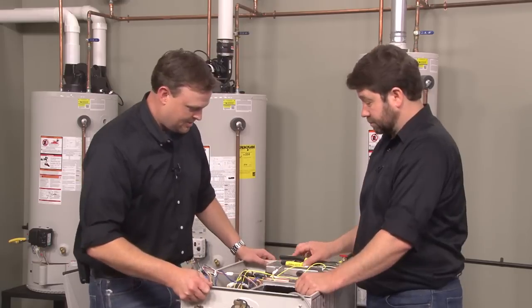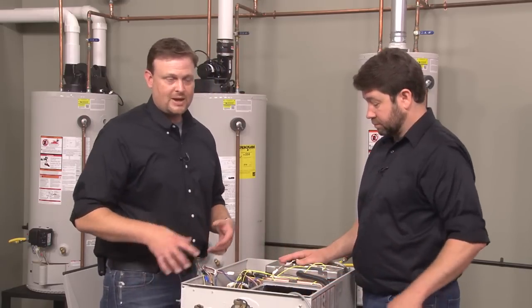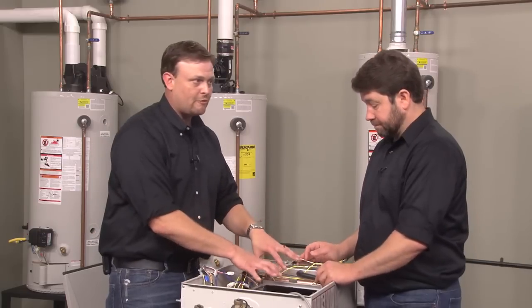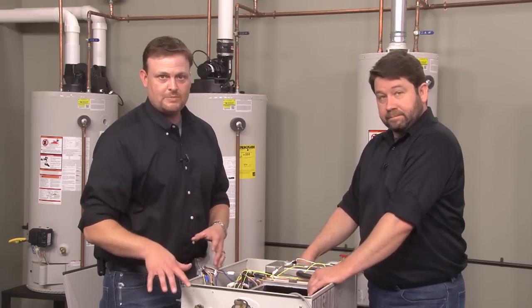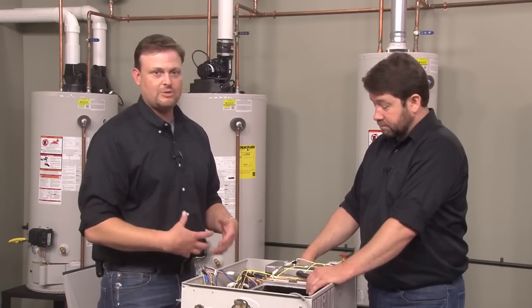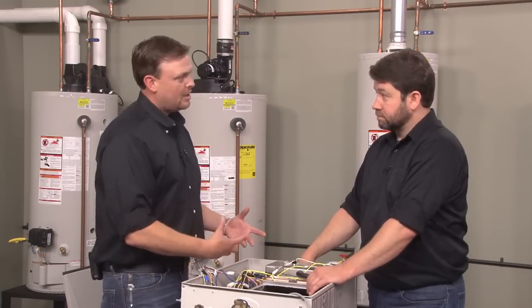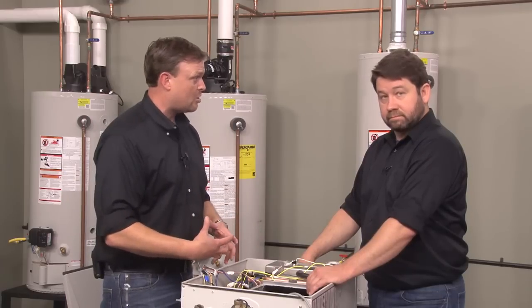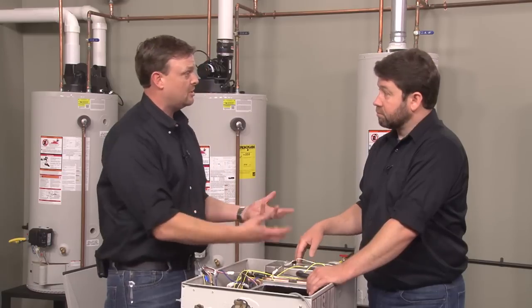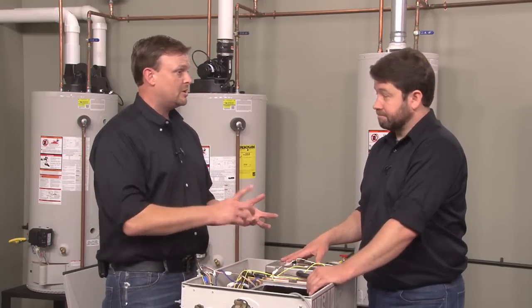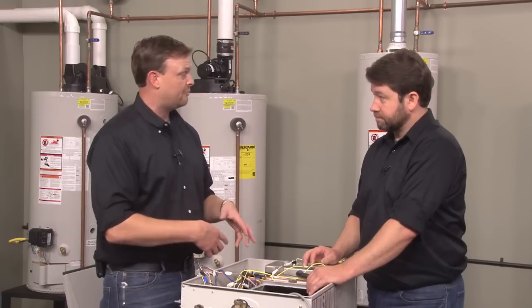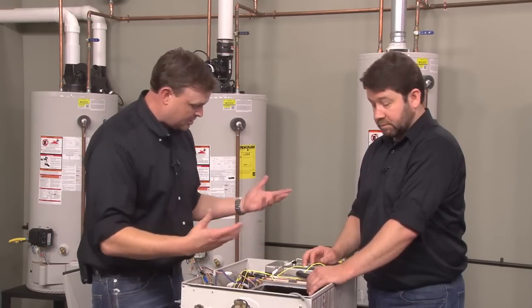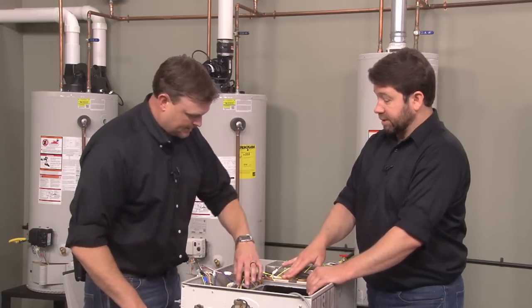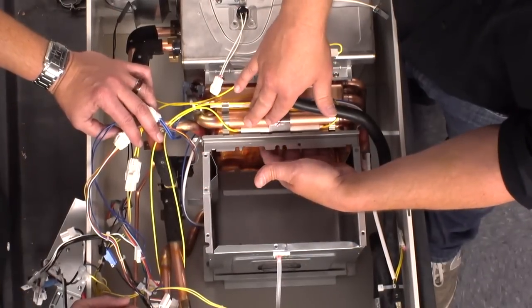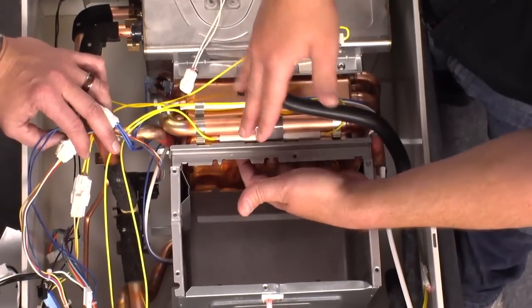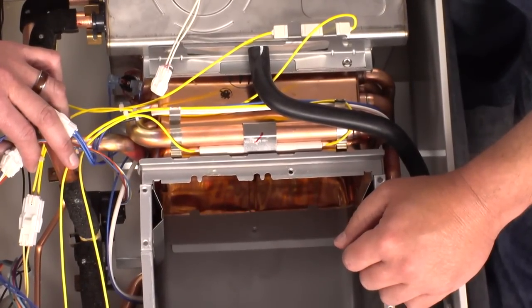Very good point. Next we're going to take off the bypass. The bypass allows us to overfire the unit at lower temperatures, like 120 degrees, getting hotter water out and mixing it down with colder water coming in from the bypass. This helps with flow not being so low at lower temperatures, and most importantly helps prevent condensation on the copper heat exchanger, since condensation is corrosive and copper and condensation don't mix well at all.